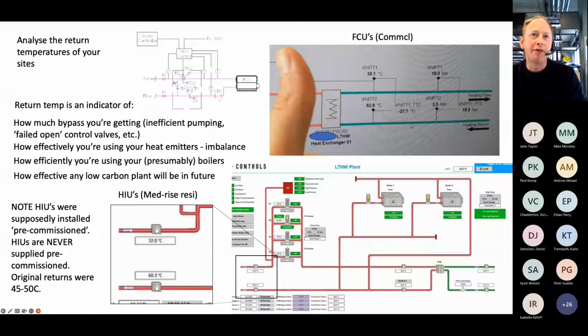Here's an example on your bottom left of HIUs, mainly HIUs and a medium rise, and you're getting a very good delta T on that one. These HIUs were initially giving you 45 to 50 on this site. It turns out that they hadn't been commissioned. They were installed supposedly pre-commissioned.